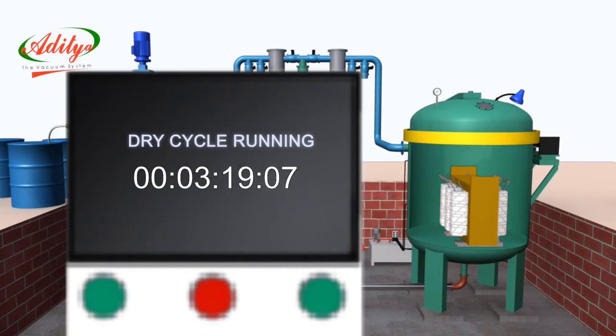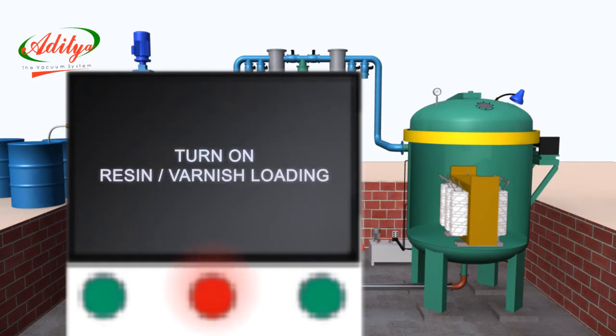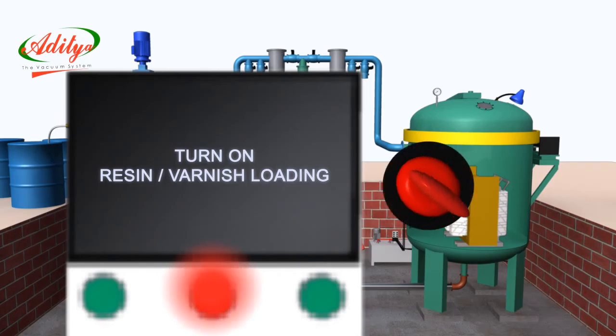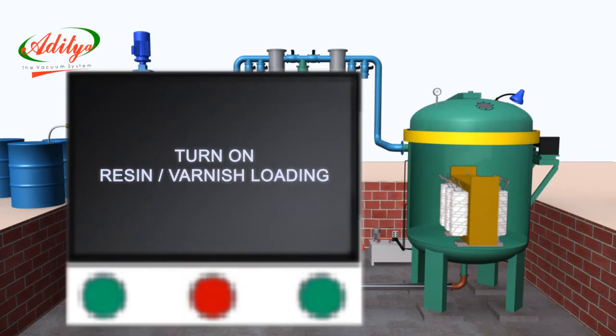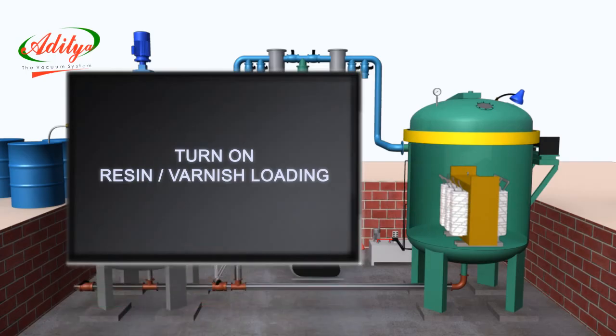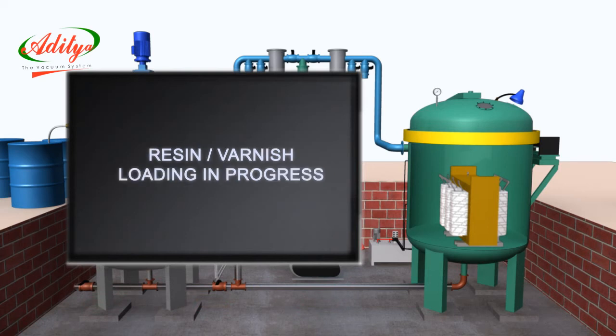Wait cycle under vacuum and resin or varnish. Resin or varnish loading. Once dry cycle is completed, hooter starts. This indicates to start the varnish loading. During this time, the display will show Turn on resin or varnish loading. The operator needs to turn the resin or varnish load or unload switch towards loading position manually. This will stop hooter, and when the operator does so, the varnish loading starts. During varnish loading period, the display will indicate Resin or varnish loading in progress.